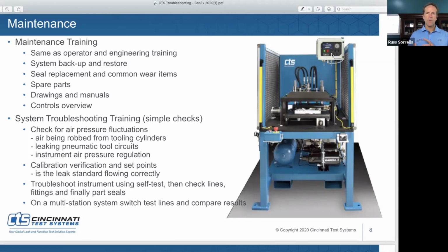So what Gordon is talking about is actually mounting a valve externally so that the air, when it's released, doesn't go back through the instrument. It exits a valve that is external to the instrument to avoid getting debris into it. Now, of course, the debris can get in the exhaust valve, but that's okay. That's the reason it exists. So we just have to troubleshoot that aspect.